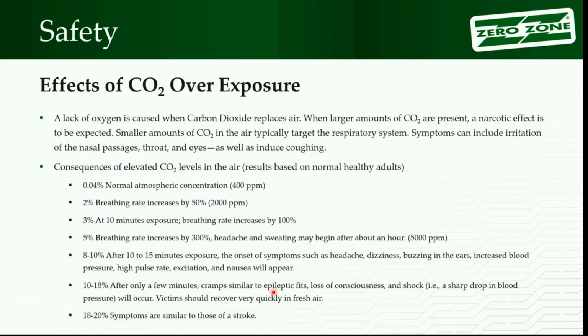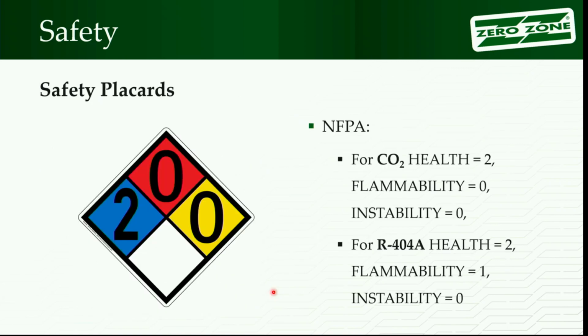So they have some numbers on that as you start going. As the CO2 gets elevated in the air, your breathing starts picking up. If you get up to 18-20%, you start looking at having a stroke. So again, CO2, like all refrigerants, can be bad, but pay attention to yourself when you're working in a room.